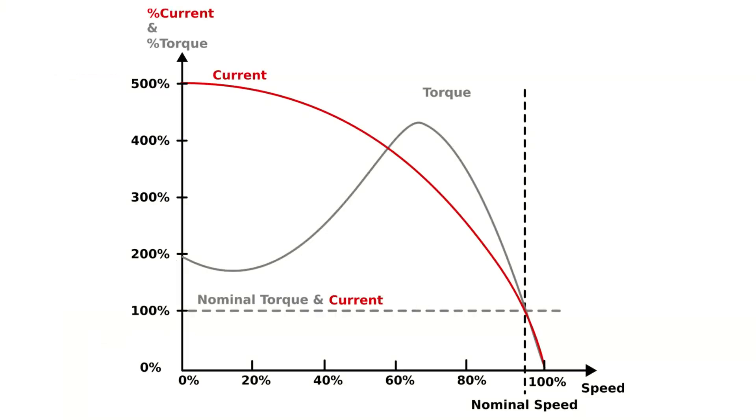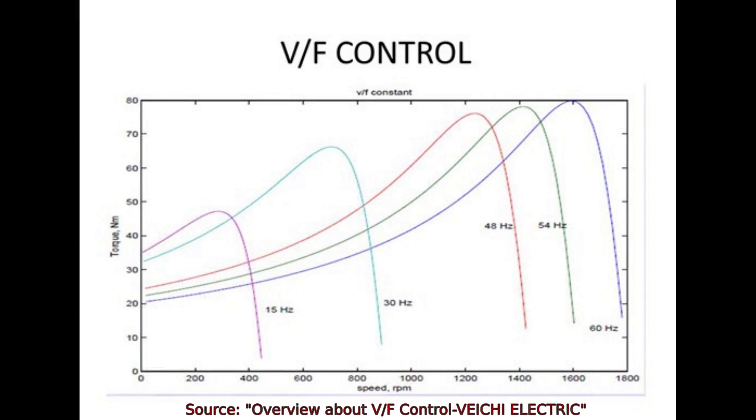There are times when the current may be higher, for example at startup, when the slip speed is largest. But that high current is only transient, and is also mitigated by the VFD, because I can start the motor with a slower frequency than the rated frequency, so the slip speed won't be as big initially. I'll leave a link in the description that goes over this point in detail.